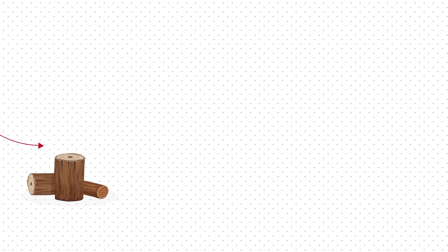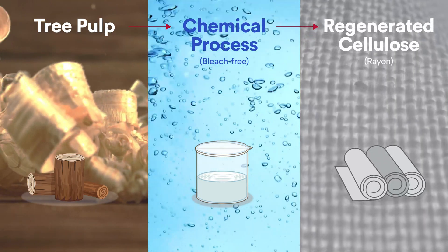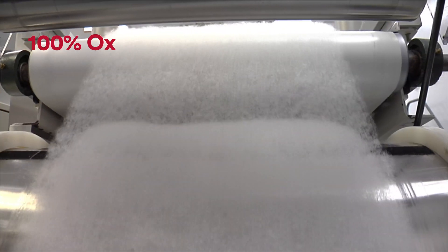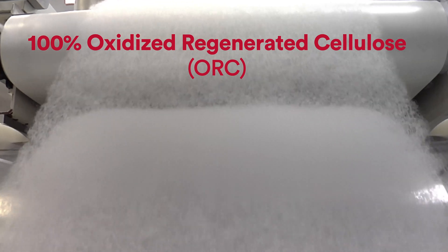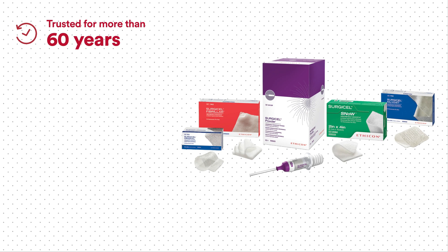This required engineering innovation. Like the rest of the Surgicel family of absorbable hemostats, Nu-Knit starts out as tree pulp that, through a chemical process, is turned into regenerated cellulose, or rayon, to create uniform fibers. The precise oxidation process is what turns the regenerated cellulose textile into the absorbable medical device Surgicel that surgeons have trusted for more than 60 years.